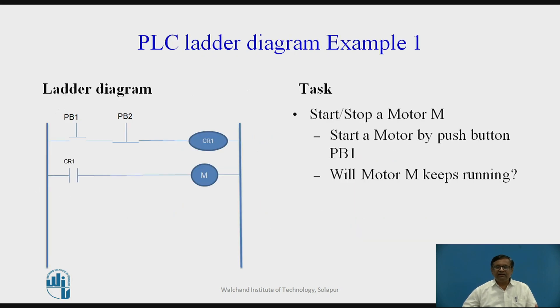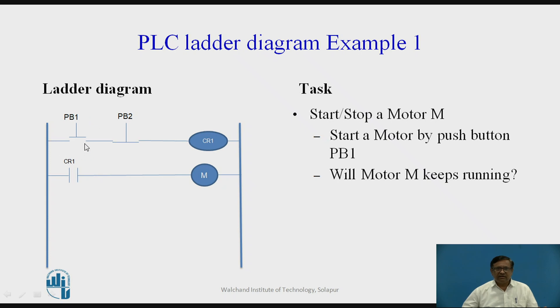Let us go to example 1 — ladder diagram example 1. Our aim is a simple ladder diagram: we have a motor and we want to turn this motor ON using push button 1 and turn it OFF using push button 2. The task is start/stop a motor M — start the motor using PB1 and stop the motor using PB2. PB1 is normally open, PB2 is normally closed, and there is a contact relay CR1.